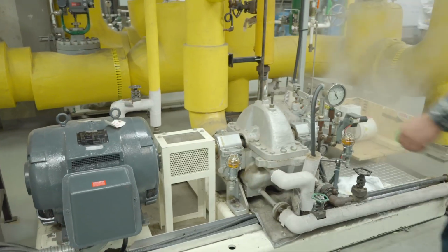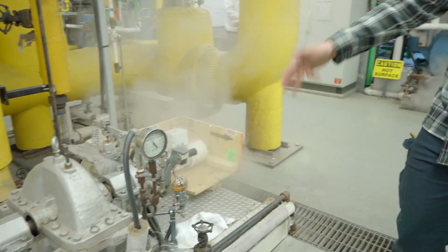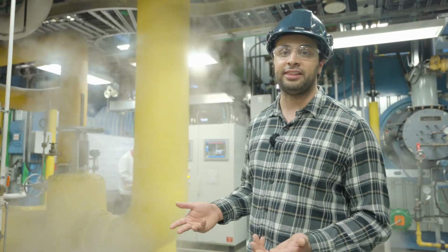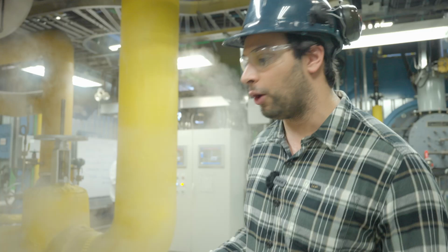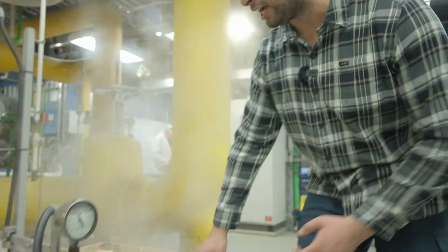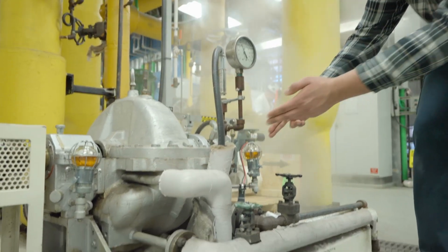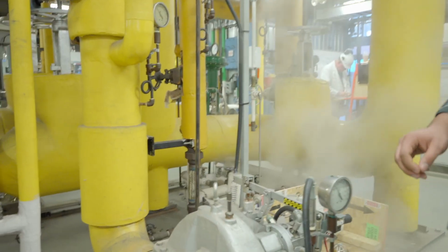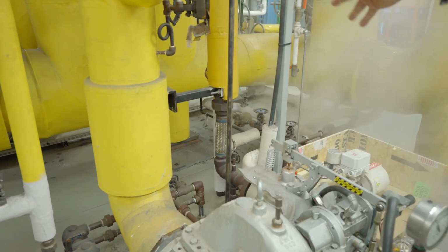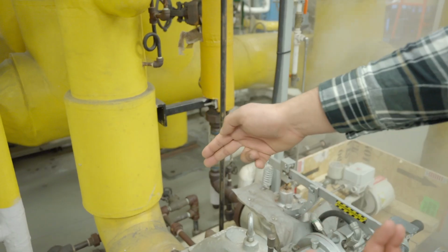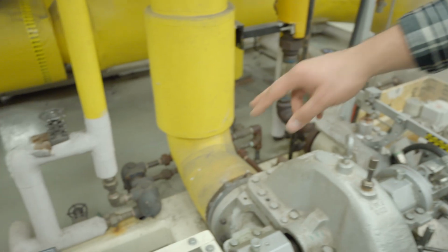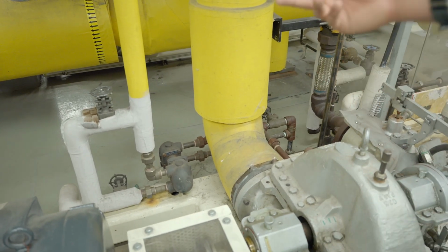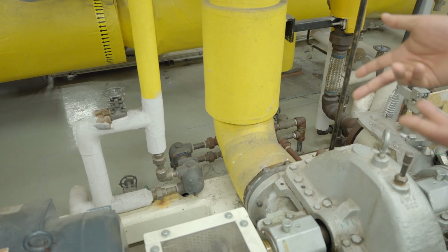One of the most important parts of turbines is that we have to have drain lines, because with steam, if it turns into condensate, that can actually ruin all the internal components. So we have multiple drain lines here. We've got two that go right into the housing of the turbine, another one just on the other side there. And on the back side, you'll notice attached to our medium and low pressure headers, we've got a couple of steam traps. We've got bypass lines. We've got the isolation valves. So obviously the isolation valves you can use if you needed to isolate it and work on the trap.